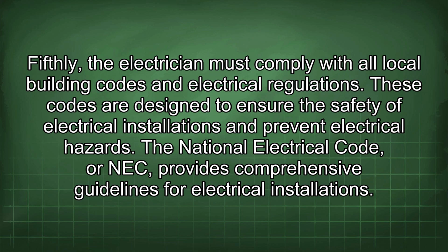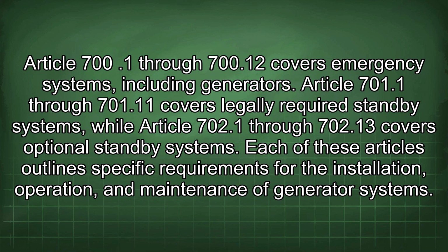The National Electrical Code, or NEC, provides comprehensive guidelines for electrical installations. Article 700.1 through 700.12 covers emergency systems, including generators. Article 701.1 through 701.11 covers legally required standby systems, while Article 702.1 through 702.13 covers optional standby systems. Each of these articles outlines specific requirements for the installation, operation, and maintenance of generator systems.